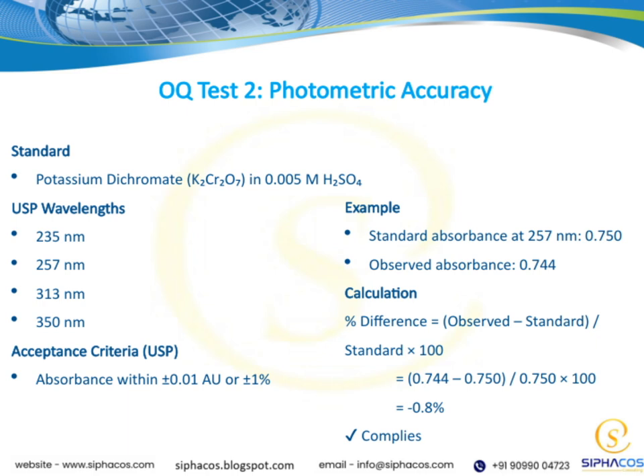Now, moving on to the overall photometric accuracy test, or OQ Test 2. We use potassium dichromate in 0.005 molar sulfuric acid as our standard. According to USP, we check absorbance at multiple wavelengths: 235, 257, 313, and 350 nanometers. The acceptance criteria specify that the absorbance should be within plus or minus 0.01 absorbance units or plus or minus 1% of the standard. This ensures our spectrophotometer remains accurate across different wavelengths, which is essential for reliable analytical results throughout the testing process.